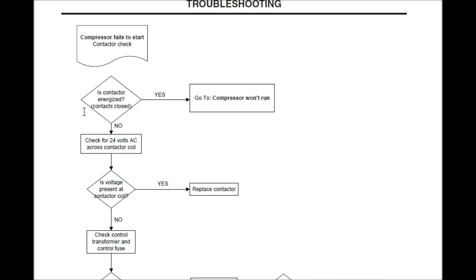Right now, we're going to say, is the contactor energized? Is it pulled in? No. So we're going to get our multimeter out. Check for 24 volts AC across the contactor coil. Now we're going to move along.